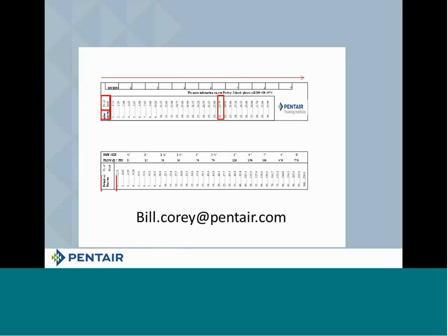If you flip the ruler over on the other side there, you're going to see it says pounds of pressure, feet of head. Now, what this side of the ruler is doing is it's measuring the discharge side of the pump. Okay? So, if I were to say that I want 50 psi, and I look down there, 50 psi comes up to 115.5. Generally, I round that off to 115, 116 feet. All depends on what I'm talking to.